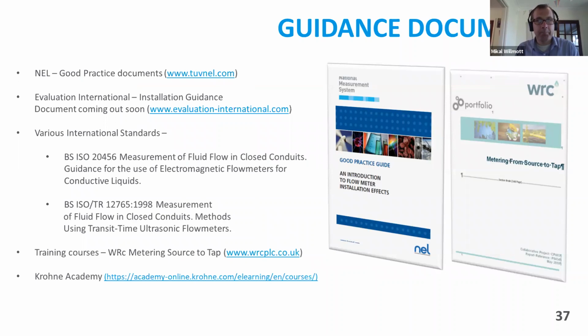Okay. All right, so there's a number of guidance documents that are available that you can look at. NEL have done a brilliant one a few years ago, quite a few documents there. Evaluation International, and I don't know of any organization over the last 10 years who've done more to test large diameter meters than Evaluation International. They have got an installation guidance document coming out soon, or it's being written up now. So again, you may want to contact them, and they're going to be looking at a lot of the testing that's been done over the last 10 years and turning that into an installation guidance.